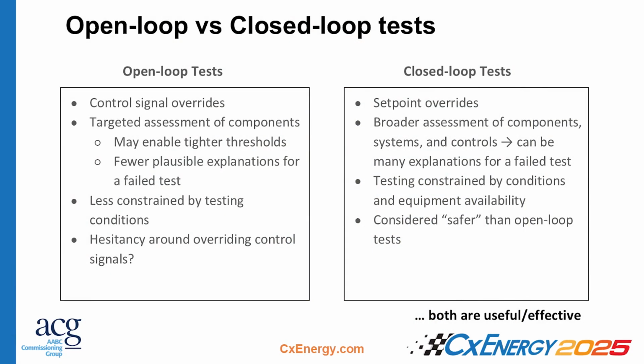So, open loop versus closed loop testing. This is a nomenclature that we use, and I want to make sure you guys are clear on this. When we talk about open loop testing, I call this a little more hacky than closed loop testing. You're really targeting specific components of your system. So with a VAV box, for instance, you're targeting the actual damper position control override and modulating that damper to either fully closed or fully open, and seeing how that control manifests itself in airflow readings, things like that. Doing that allows you to have a more targeted assessment of the components and also gives you fewer plausible explanations if you do have a failed test.